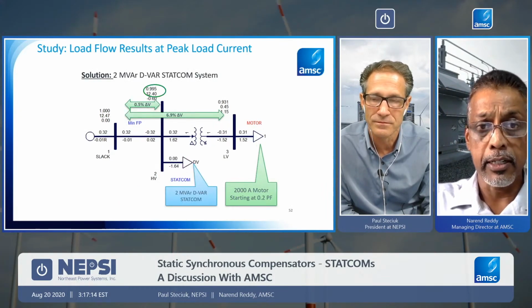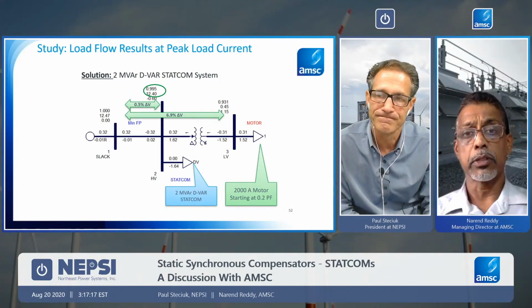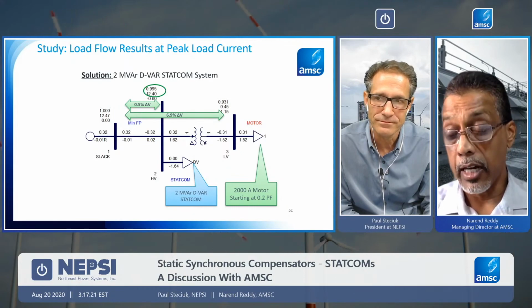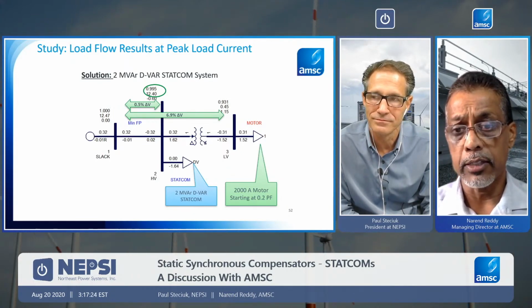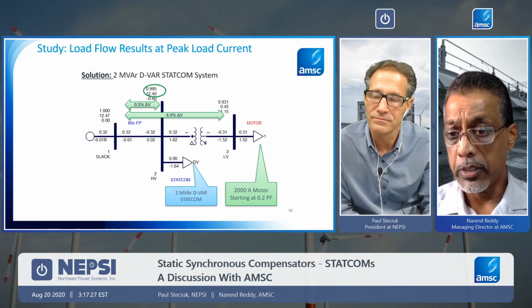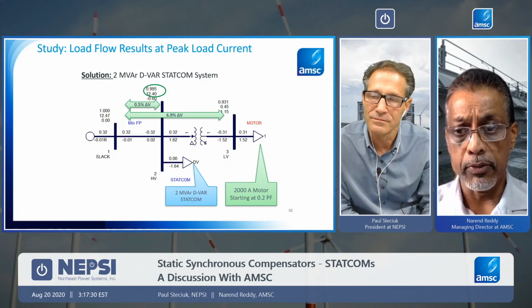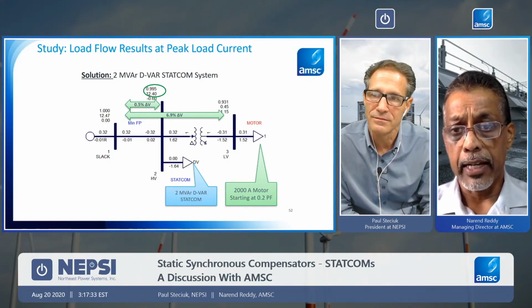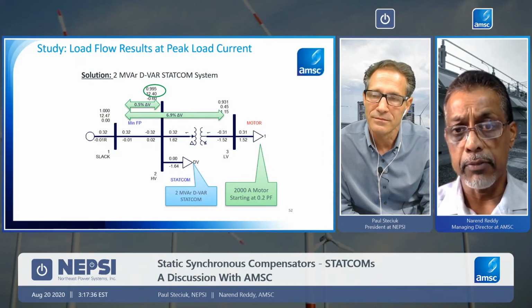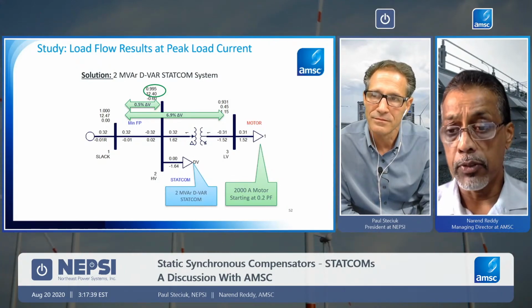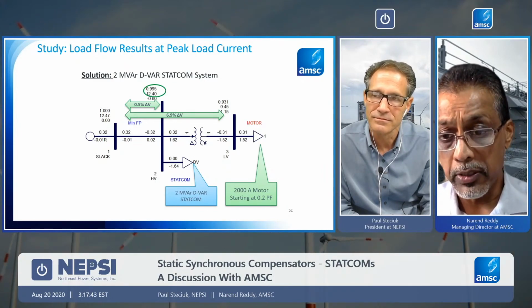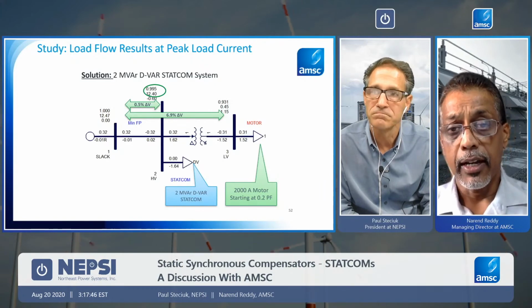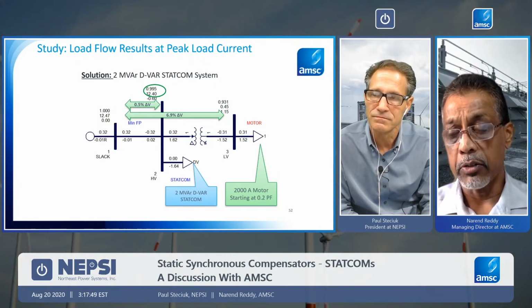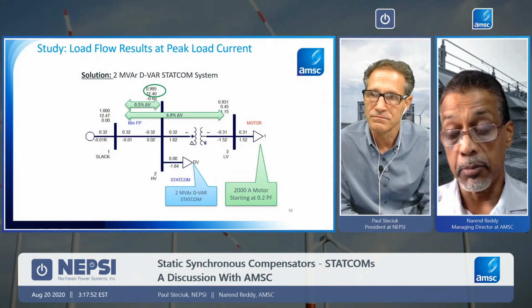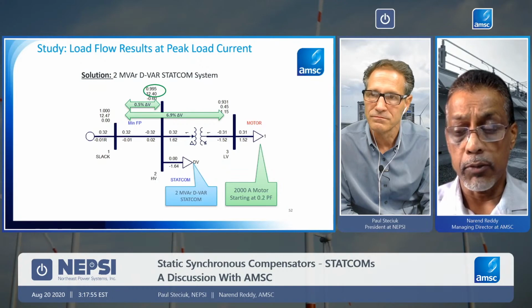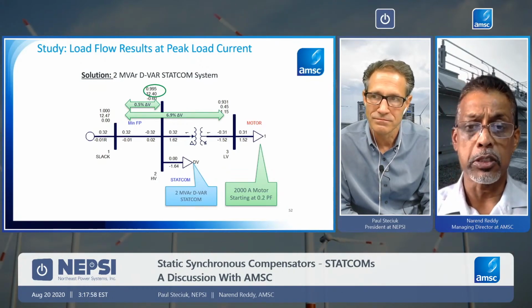In this case, the utility worked with us, came to us and put us in touch with the customer, and we looked at various different options. Here's an example of how we used a small 2 megavar rated device, which is very adequate for the size of the load in this particular case. Just by connecting that dvar to the medium voltage bus, we improved the flicker from closer to 6% at the connection point to less than 0.5%. That also gave almost a 6% improvement in the voltage inside the facility, at the motor terminals.